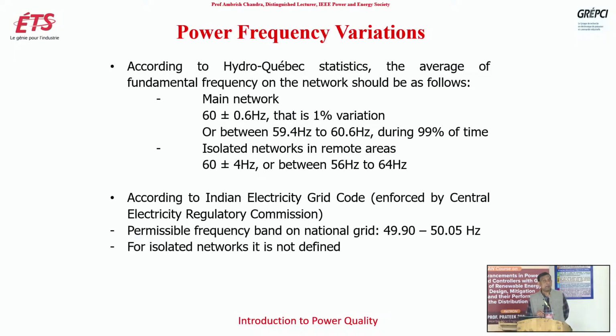Isolated networks in remote areas, because there are so many remote areas, and I will discuss that also later on, why there are so many remote areas and why we cannot connect the grid to those remote areas, because they are thousands of kilometers away and it is not economical to put a transmission line there. So there are 200 communities living in the north of Canada which are not connected to the main grid. They are totally dependent, 100%, on diesel generators. So that is the topic. After 2-3 lectures I will be discussing this. So in isolated networks in remote areas, 60 plus minus 4 Hertz, or between 56 Hertz to 64 Hertz. Because it is a small power network, and in a small network, even a small variation counts.